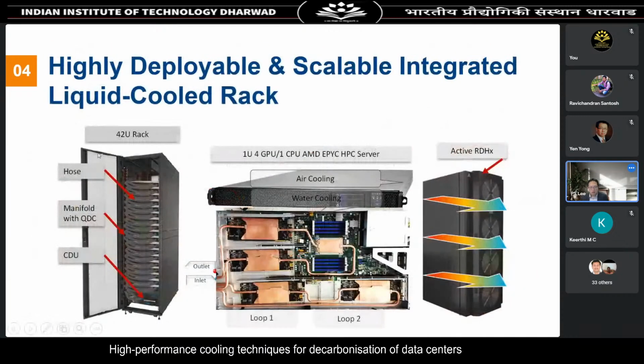After integrating the cold plate into the servers, we integrate into standard 42U racks, as shown here. In one configuration we tested, it also comes with an active rear door heat exchanger, which allows us to discharge all the heat picked up from liquid cooling into the hot aisle, avoiding the need to lay piping connecting a centralized coolant distribution unit to the liquid cool racks.